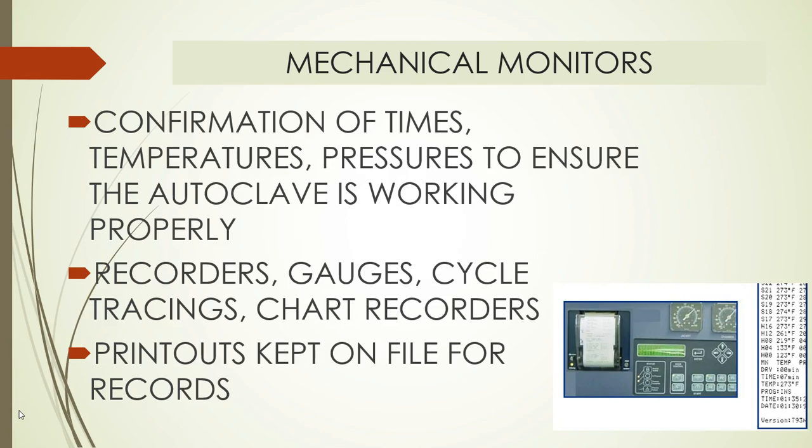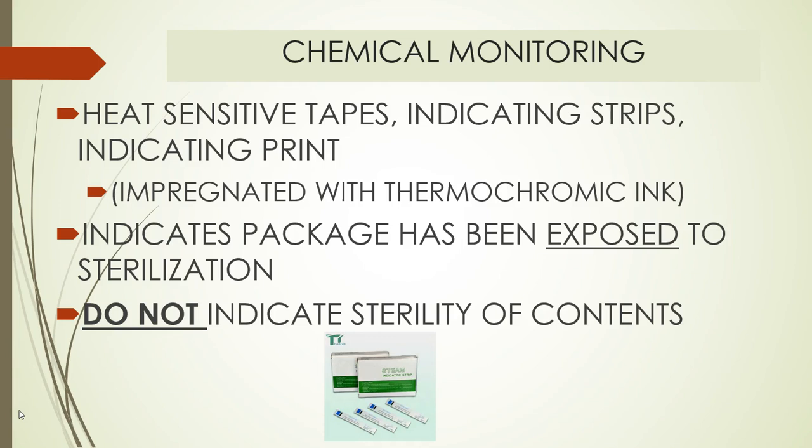So here again, you may want to consider placing that in your manual, that the individual doing the autoclaving is responsible for evaluating the information that's available from the mechanical monitors and confirming that an appropriate time, temperature, and pressure was achieved. The chemical monitors are commonly utilized by many podiatric physicians.